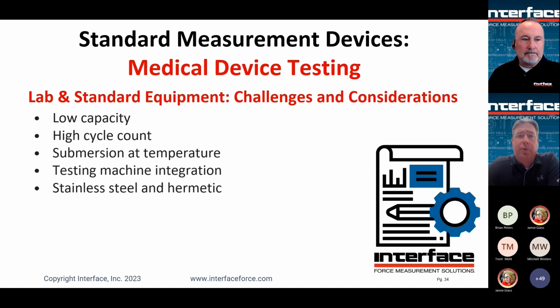Challenges and considerations for medical device type testing. Generally speaking, we're looking at devices that are going to be tested at lower capacities. Lower capacities bring different challenges. Perhaps they're going to be more susceptible to outside influence. So all of a sudden you're worried more about how the cable of the load cell is restrained and how the load string is applied. The environmental condition can have a relatively higher impact on your results.